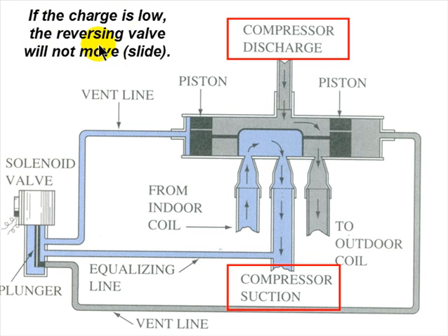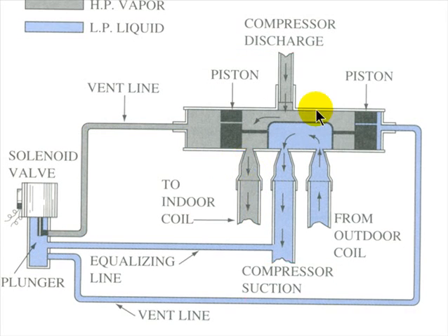If the charge is low, the reversing valve may not slide or move because you don't have a high side and a low side, and if there's no differential pressure because your pressure is low, then it's not going to move. Now, we moved it the other way. This is still connected to the compressor discharge, the discharge line from the compressor.